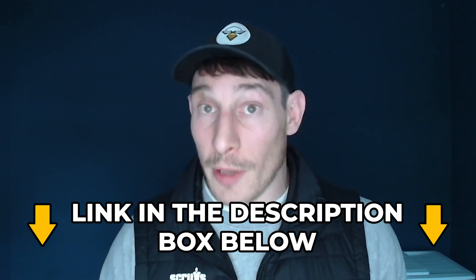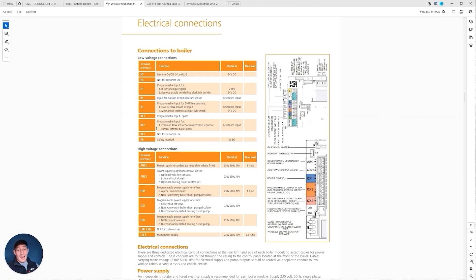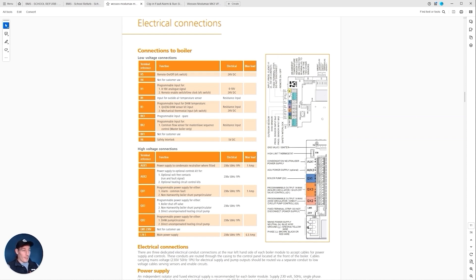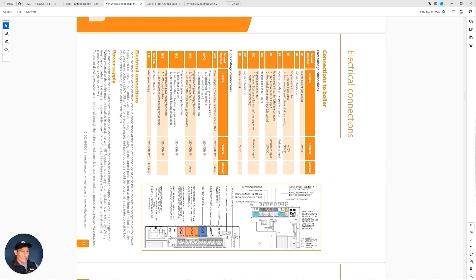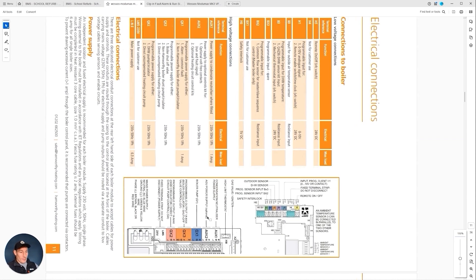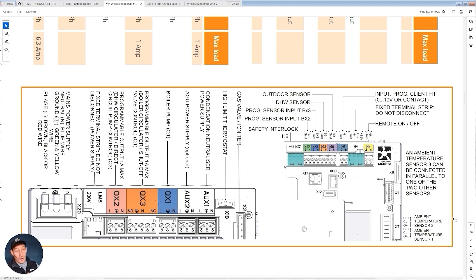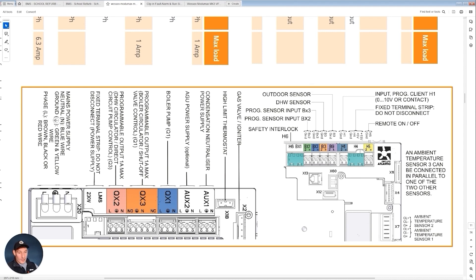Now for the electrical connections, this is really what we're interested in in this tech manual, page 11. I'm just going to turn this on its side so we can zoom in here. I'll tell you now, ultimately all we're using in terms of all of these connections is the 230VAC power supply that we're feeding into the boiler and H1.